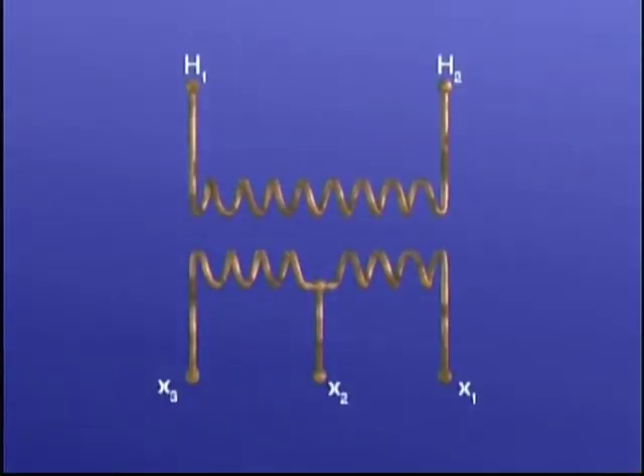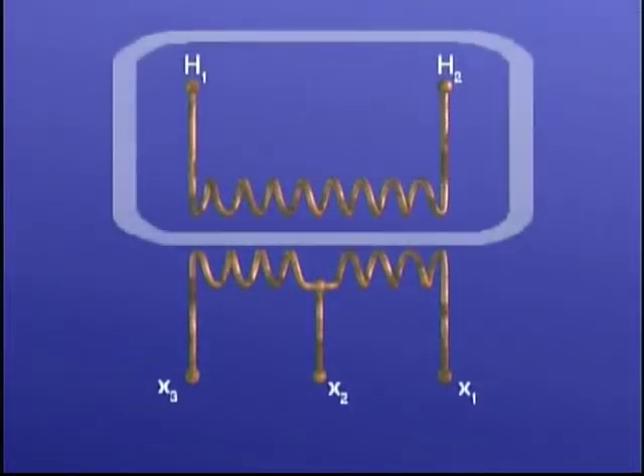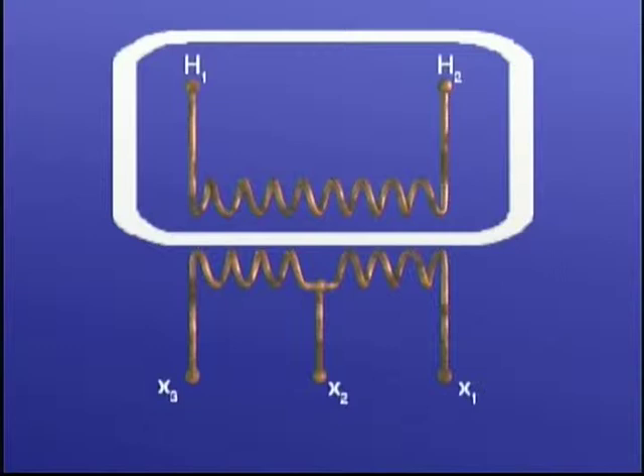We'll use this simplified illustration of the primary and secondary winding in a single-phase transformer to demonstrate the internal connections that we shall refer to as conventional transformer wiring. Now here's the primary winding of the unit. One end of the winding is connected to the H1 bushing on the transformer. In this example, the other end of the winding is connected to the H2 bushing on the transformer.